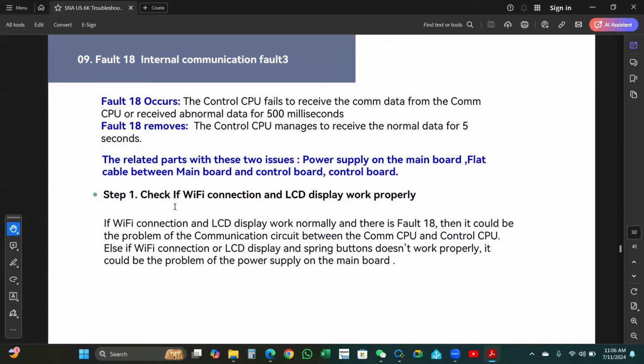Step 1. Check if the Wi-Fi connection and LCD display work properly. If Wi-Fi connection and LCD display work normally and there is a fault 18, then it could be the problem of the communication circuit between the COM CPU and control CPU. Else, if Wi-Fi connection or LCD display and spring buttons doesn't work properly, it could be the problem of the power supply on the main board.